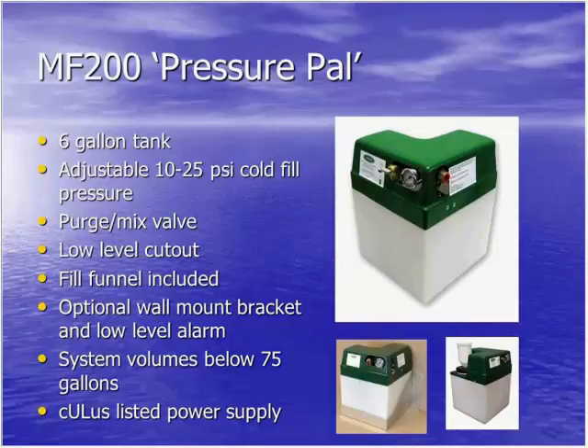If the pressure were to continue to drop 5 psi below that set point, a second set of normally closed contacts open, and then you can use that to tie into the building management system, have some sort of interlock on the boiler or water heater, whatever it may be. This particular unit is also recommended for systems that have about 75 gallons or less. And it comes with a UL listed power supply as well.